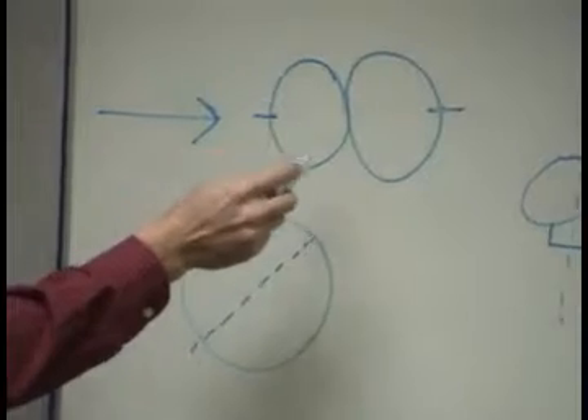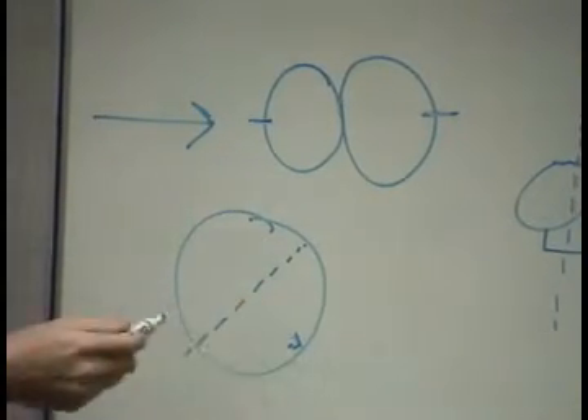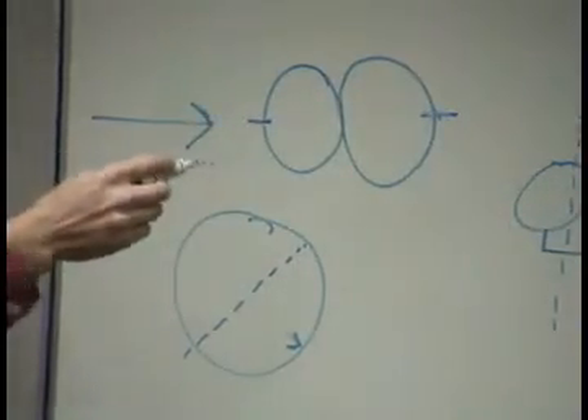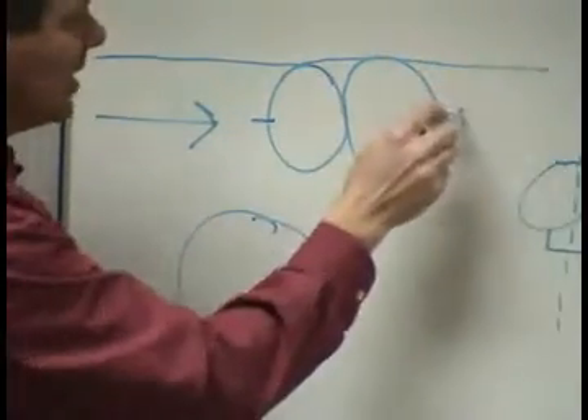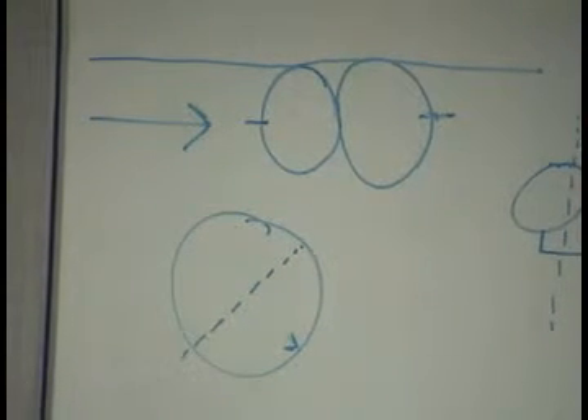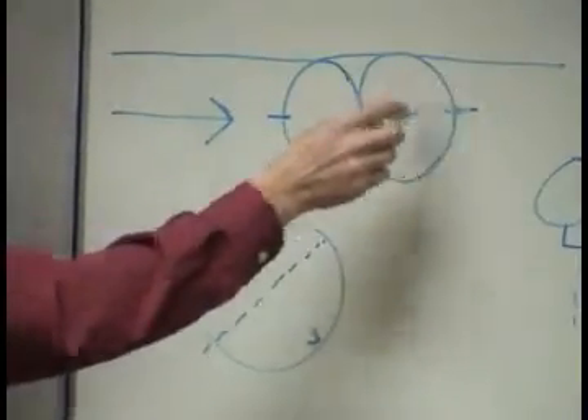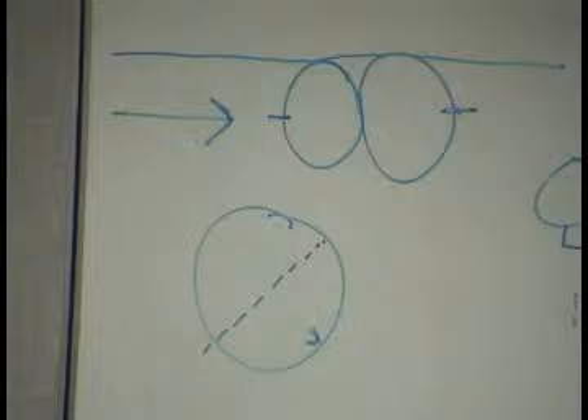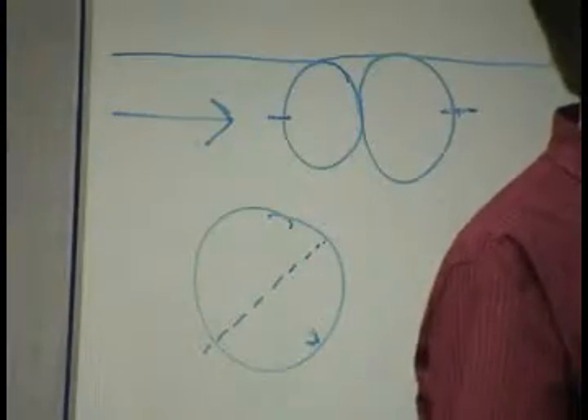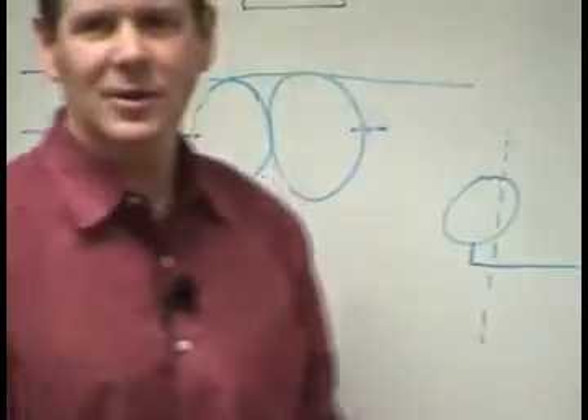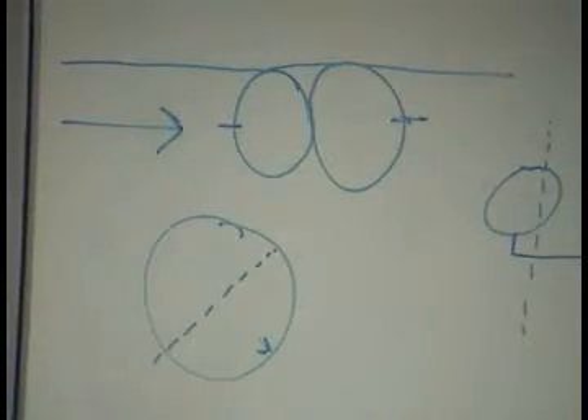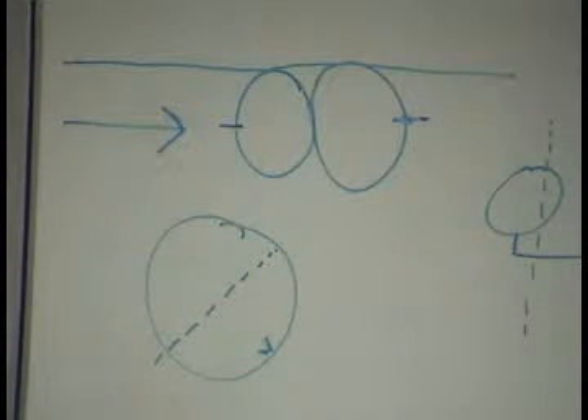And instead of reading static, or the pressure against the side of the duct, what they're reading is this downstream pressure. So your air is flowing along here, it goes along here, and this kind of creates a little vortex, a little low pressure area. So instead of the normal static pressure, you get something a little bit less because you're getting a little vortex off of that. So they're saying, with our box, they call it the K factor, our K factor is not 4005 like you're using. Ours is something else. And so instead of having 0.04 to get 300, they'll throw out things like ours is 1.7 times greater than that. It's really amplifying the crap out of that signal.